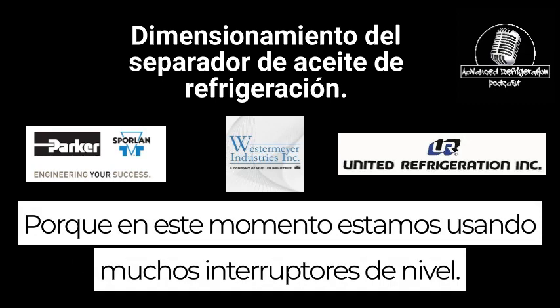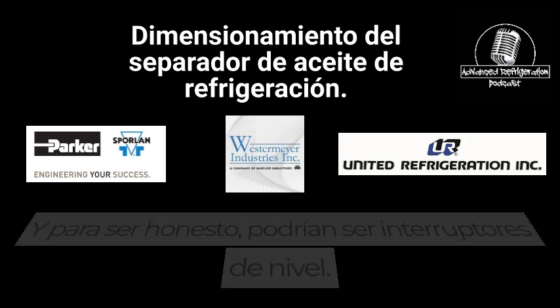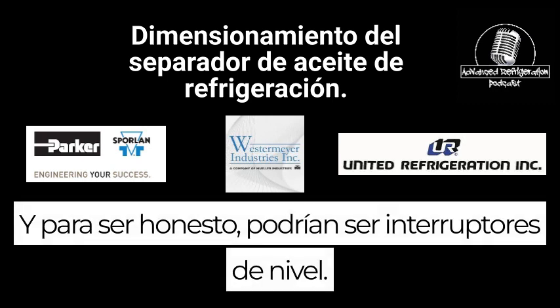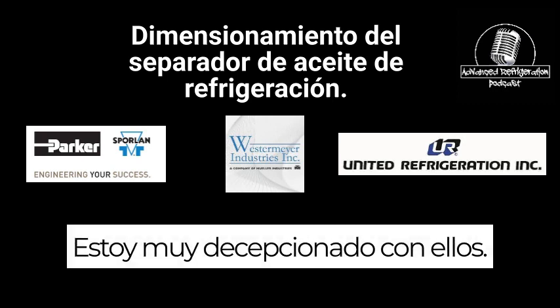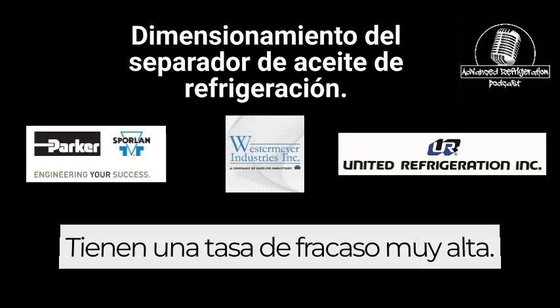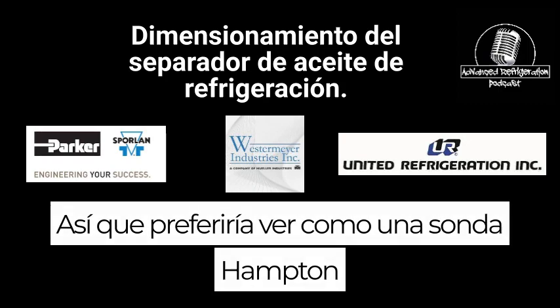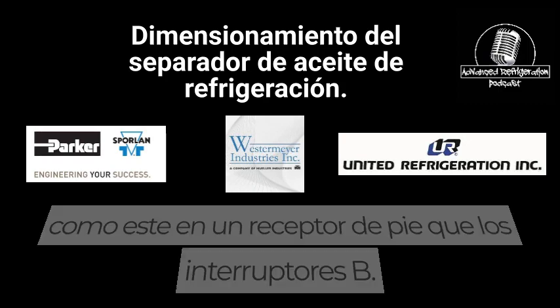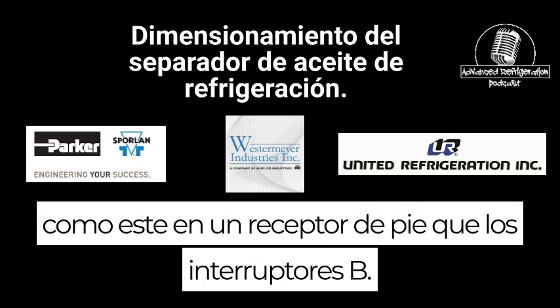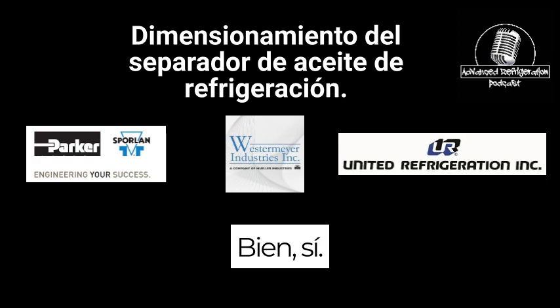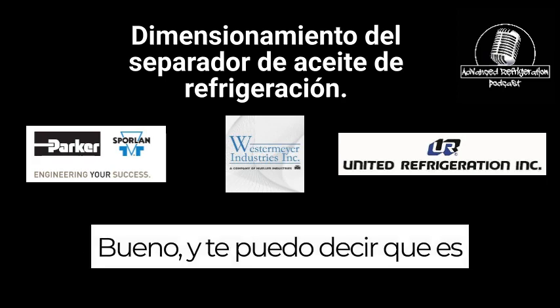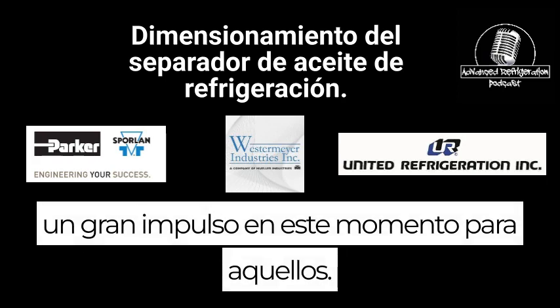Right now we're using a lot of level switches, and to be honest, I'm very disappointed with them. They have a very high failure rate, so I would much rather see a probe like this in a stand-up receiver than those switches. Right. And I can tell you that it's a big push right now for those.